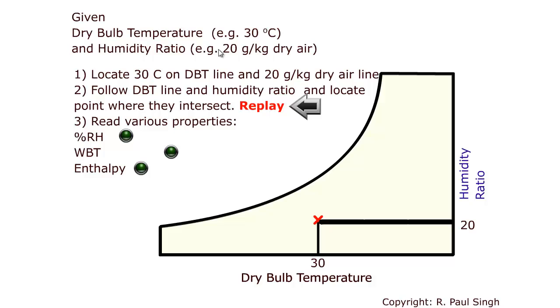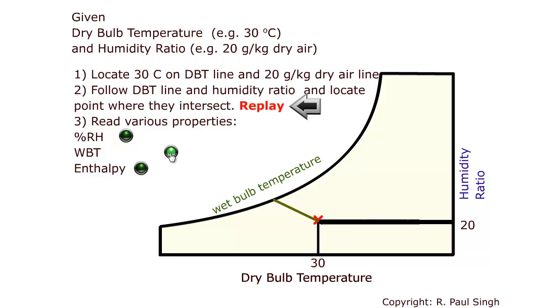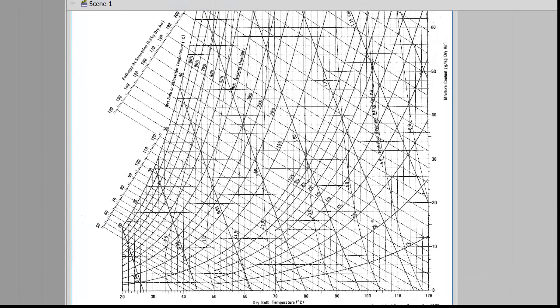In this example, the dry bulb temperature is 30 degrees C and humidity ratio is 20 grams per kilogram dry air. On the chart we identify the point at 30 degrees C dry bulb temperature and 20 grams per kilogram humidity ratio. Once that point is located, we read the relative humidity from the relative humidity curve, the wet bulb temperature along the wet bulb temperature line, and extending that line further gives the enthalpy value. By knowing two independent properties we can identify a point on the psychrometric chart and read all other remaining property values following these procedures.